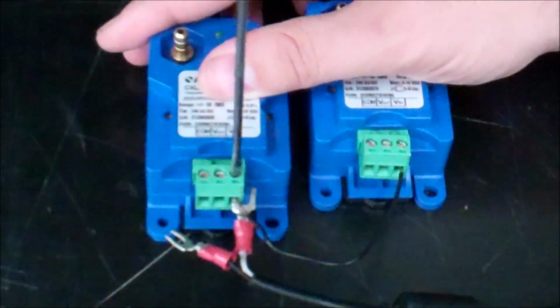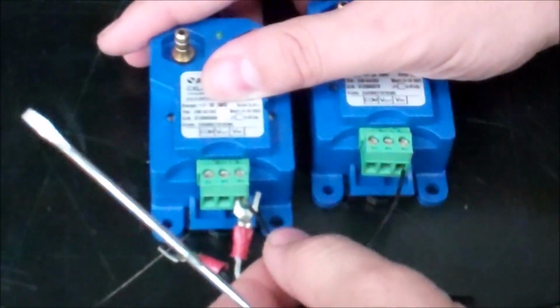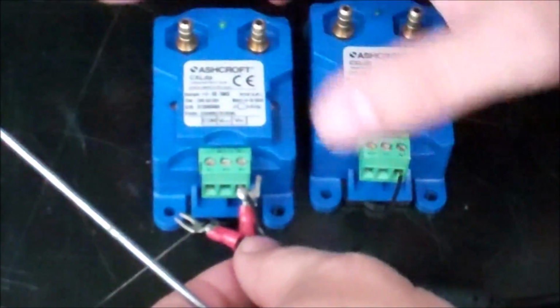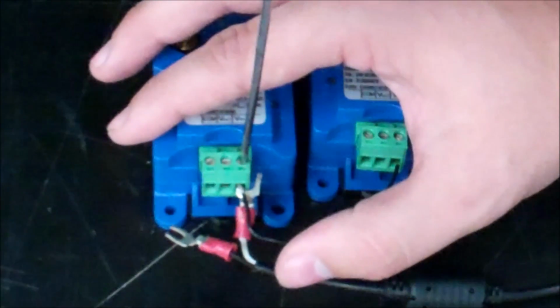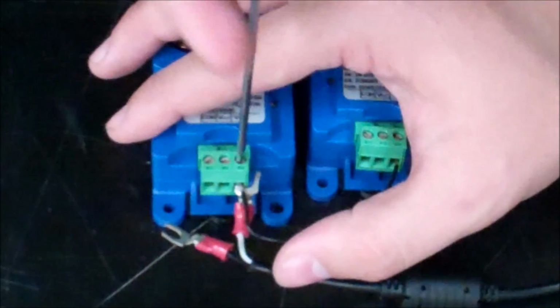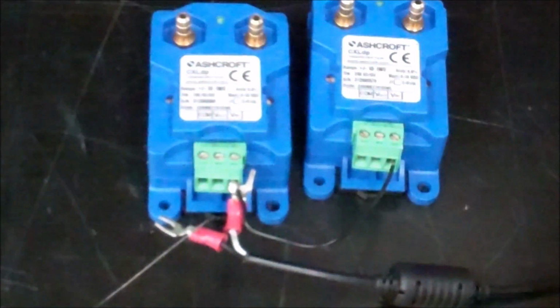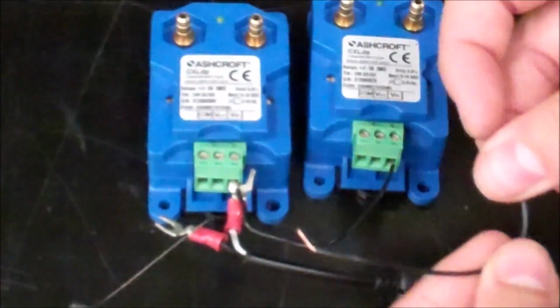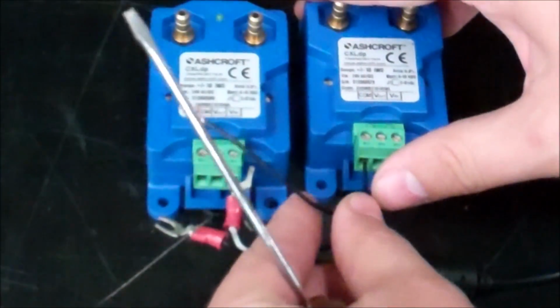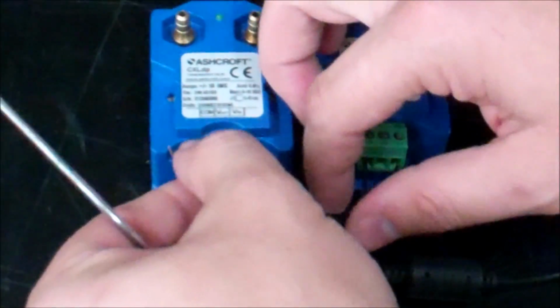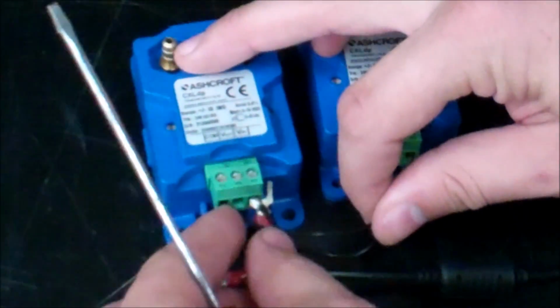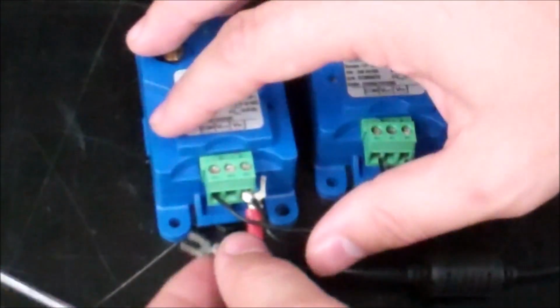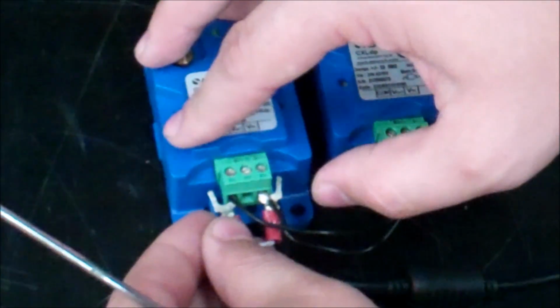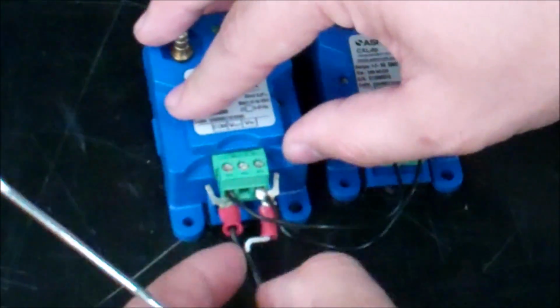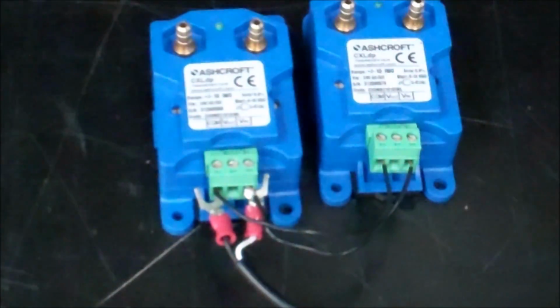Now make sure that before you can start this that you've unscrewed the terminals enough to allow for both wires to come in at the same time. Then tighten it. Now I'm going to take this black wire from my COM side and stick it into the one pressure transducer. And then I'm also going to stick in the input part, the COM part of the power supply.